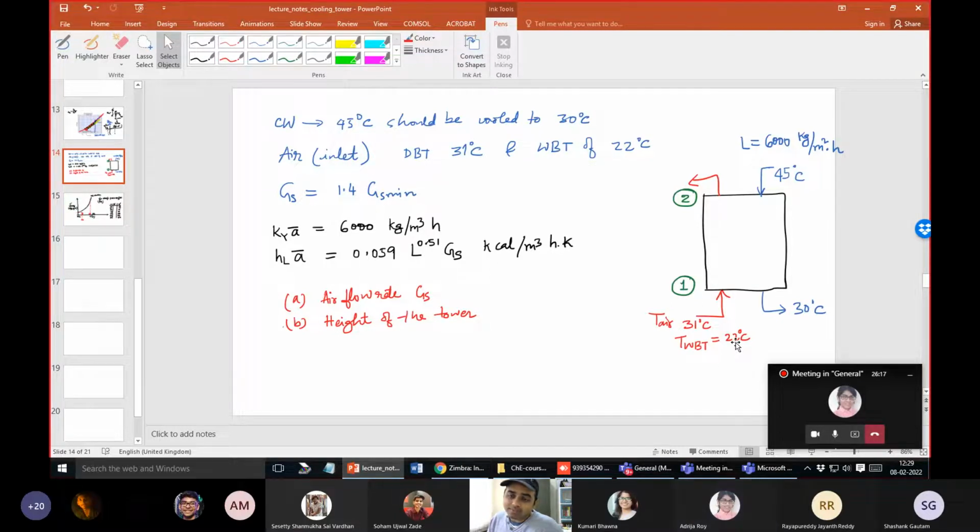Because if you do it with the relative humidity, it will get you wrong. You have to do it with the percent humidity if you want to do that sort of interpolation. Relative percent is also not acceptable, because relative humidity talks about the ratio of partial pressures. So you want the ratio of the humidity values. Okay, sir. So I'll have to convert the percent RH to percentage humidity. Yes.